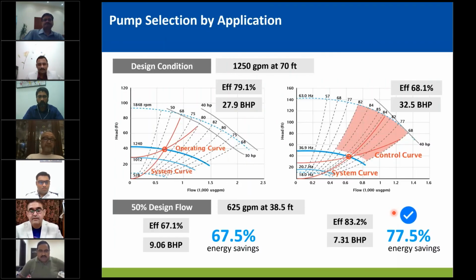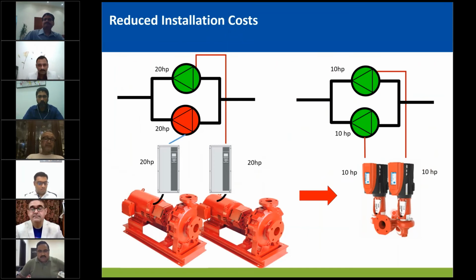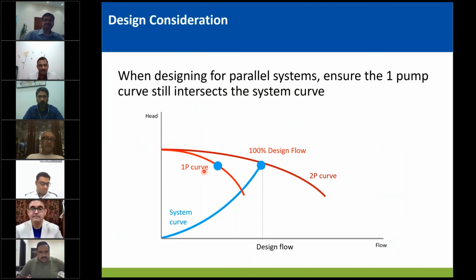Yeah, so let me go to the slide quickly. When you select parallel pumps and the second pump is failing, you will see the first pump curve coming to the end and cutting the system curve. At this point of operation, you will know what power it needs, and the motor should be sized appropriately so the motor is not overloaded. So that's how we size it, looking at the pump curves and where it intersects the system curve, and appropriately sizing the motor.